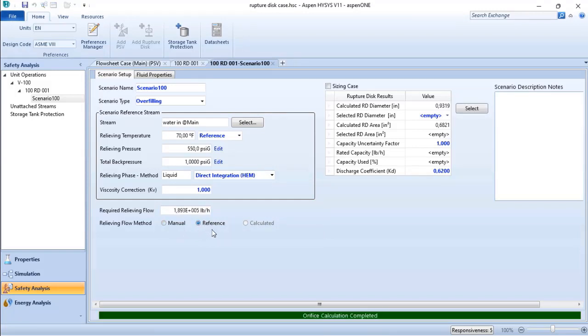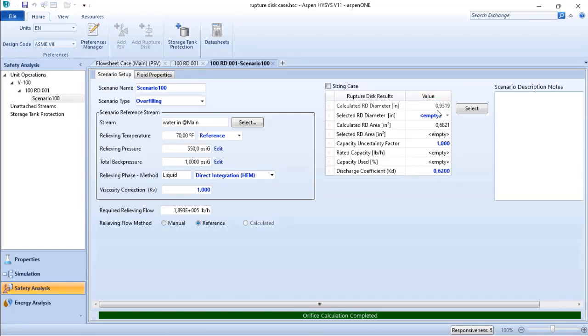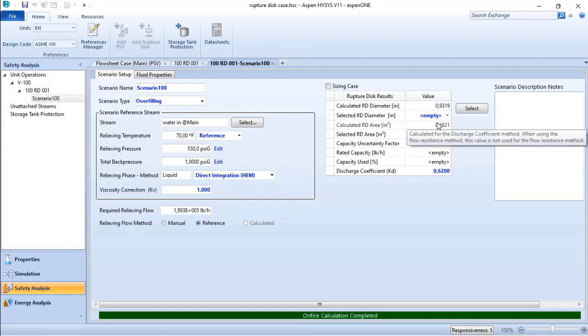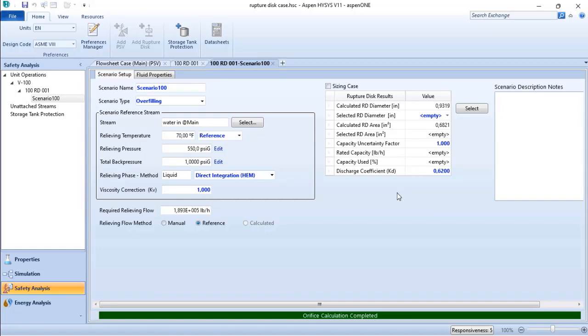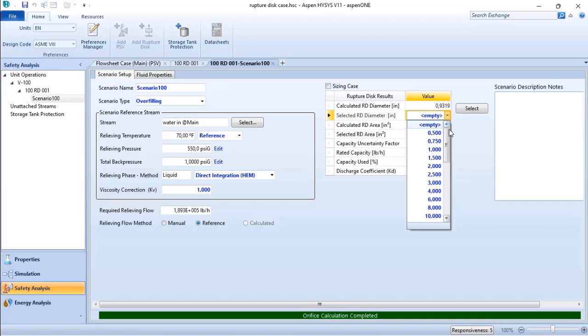Based on that, ASPEN HYSYS already performed the calculations for the ruptured disk. Here we have the diameter of the ruptured disk, and below you have the area needed to comply with this flow.